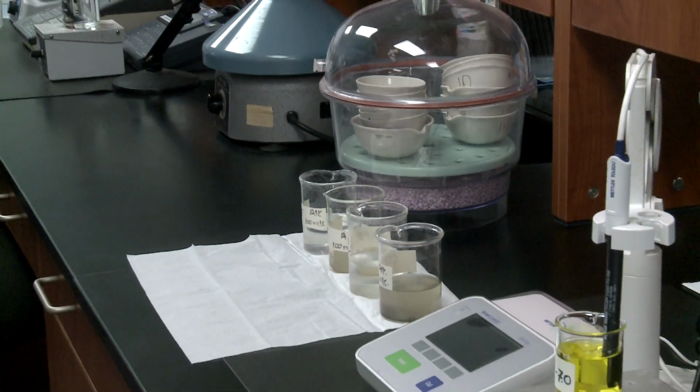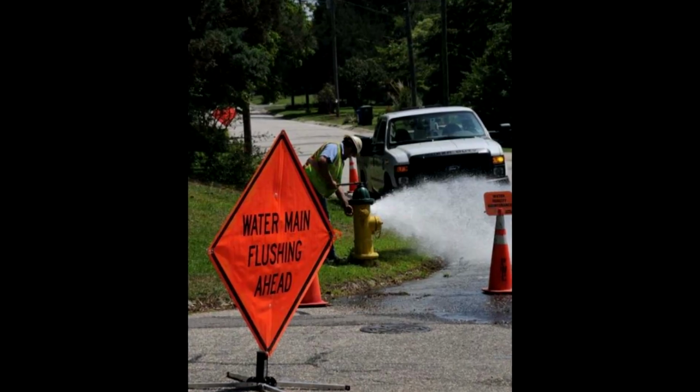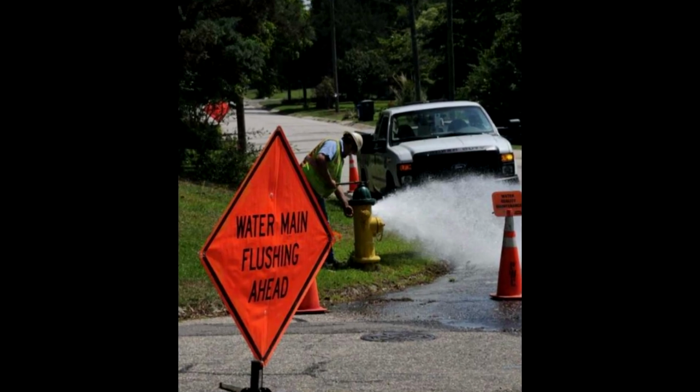He'll then bring the samples back to the laboratory to be tested. Once those go for 24 hours, we can determine whether there's coliforms present, and all the while our crews are flushing those lines, working to get the pressure back to where it needs to be. In the meantime, we will go back out and check chlorines throughout the system to make sure we have at least 0.2 milligrams per liter of chlorine residual.